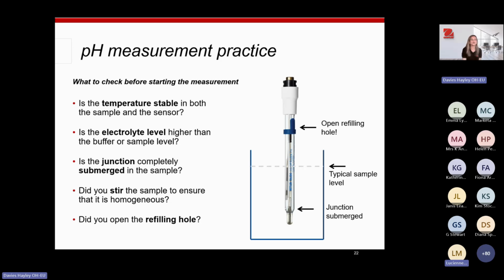Okay, so we'll carry on. I'm conscious of the time. So we did mention refillable electrodes. This is one of our refillable electrodes from our parent company, Mettler Toledo. And this is what we mean by refillable. There's a little bung here that you can open. And once it's open, if it's not in a solution, all the electrolyte will fall out of the junction. Then you would re-clean that, and then refill it with the electrolyte solution.